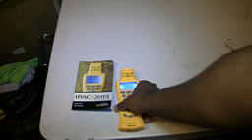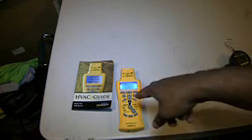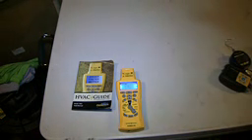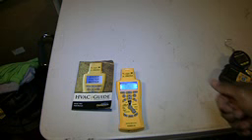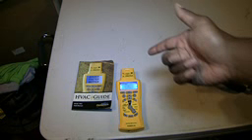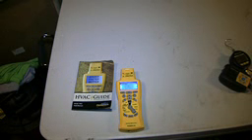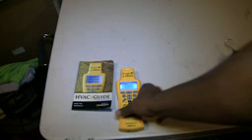Now, you still will need to know whether or not, let's say with this thing, you can measure the airflow coming out of a register, or airflow going into a return. Now, according to the instructions, you have to find out what the manufacturer's free area is on that particular grill or register. And if you don't know, the cool thing about this that Fieldpiece has done, I'm going to show you here in a second.